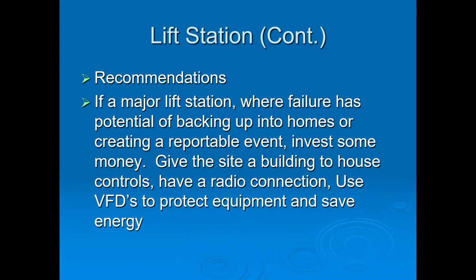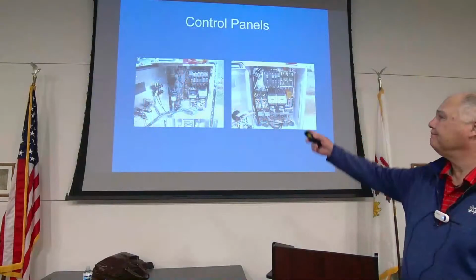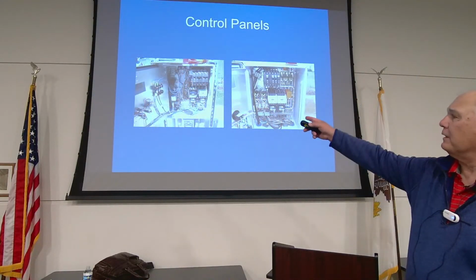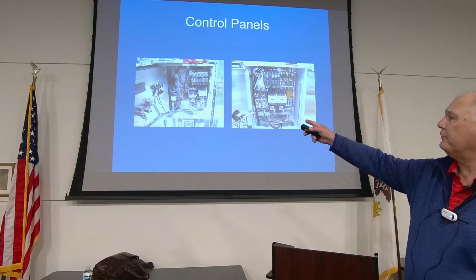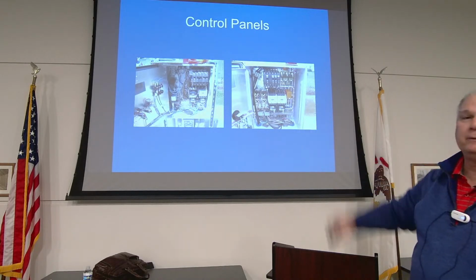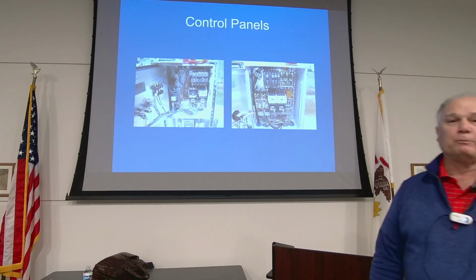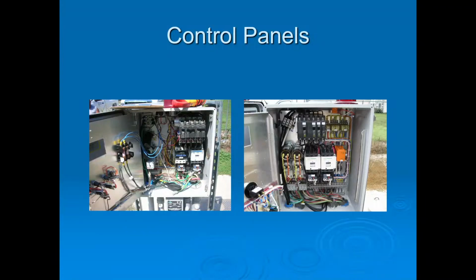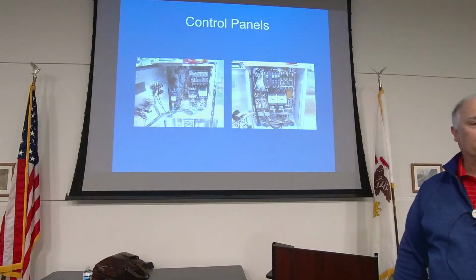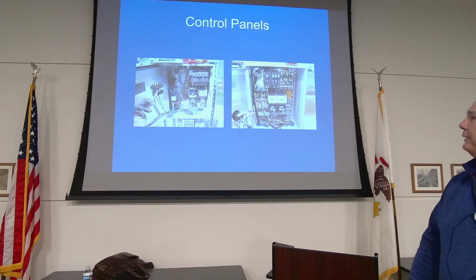Couple things that are unique. What's wrong with the station on the left? This is what it was before we fixed it. This is what it was after we fixed it. For people that do electrical work, the one on the left is not good. The reason why it's not good is you've got some exposed fuses on the door that are 230 volt, single phase. This thing looks like your fishing reel, not very good wiring.